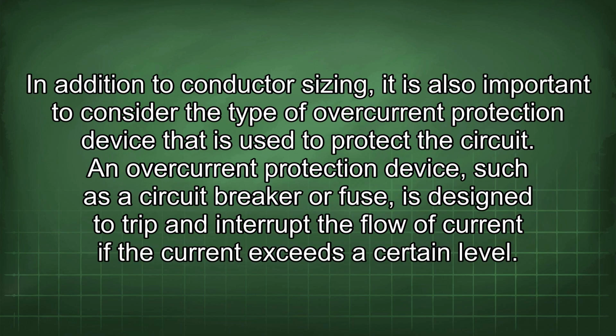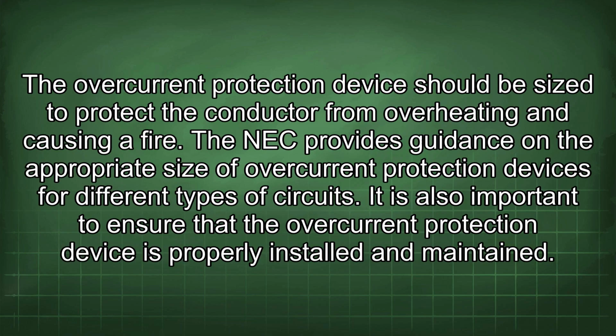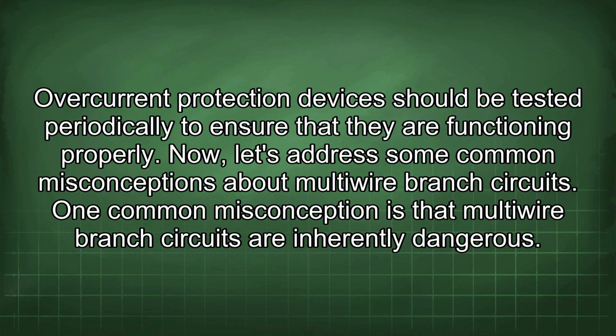In addition to conductor sizing, it is also important to consider the type of overcurrent protection device that is used to protect the circuit. An overcurrent protection device, such as a circuit breaker or fuse, is designed to trip and interrupt the flow of current if the current exceeds a certain level. The overcurrent protection device should be sized to protect the conductor from overheating and causing a fire. The NEC provides guidance on the appropriate size of overcurrent protection devices for different types of circuits. It is also important to ensure that the overcurrent protection device is properly installed and maintained. Overcurrent protection devices should be tested periodically to ensure that they are functioning properly.